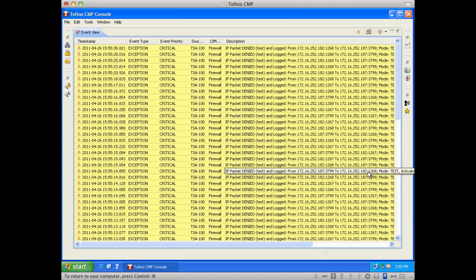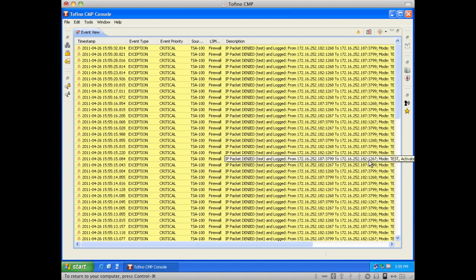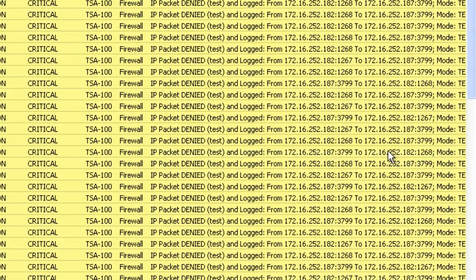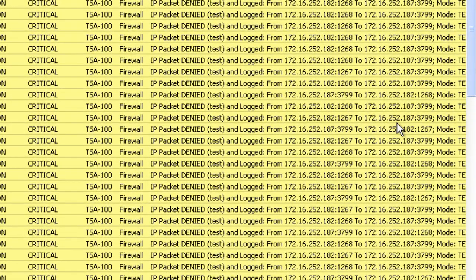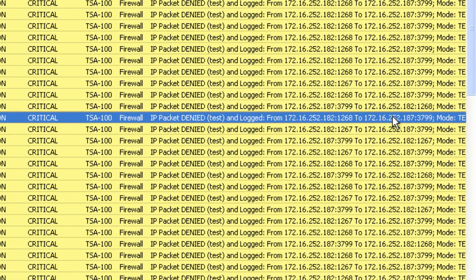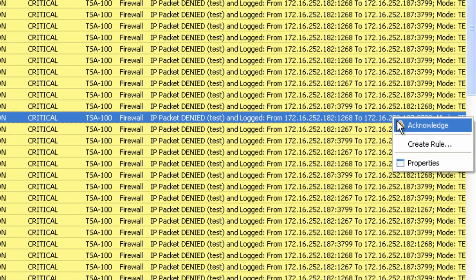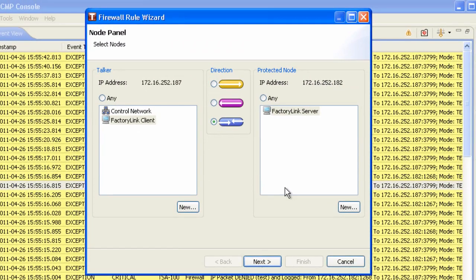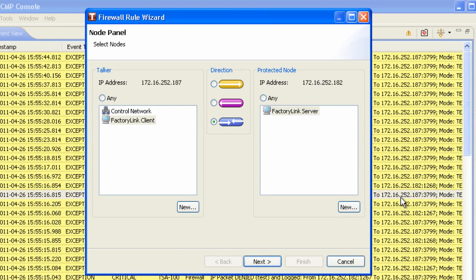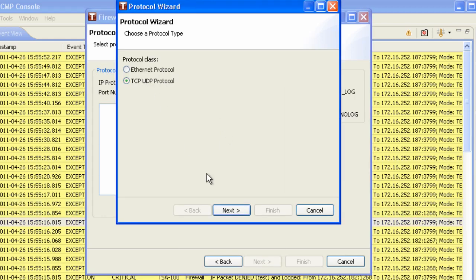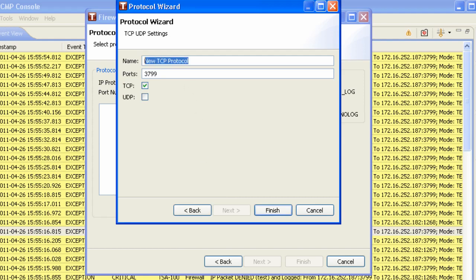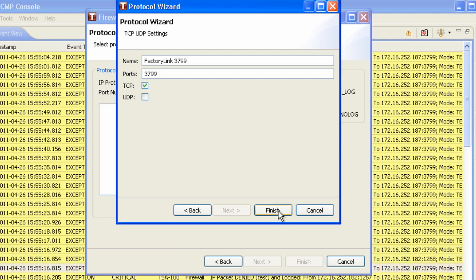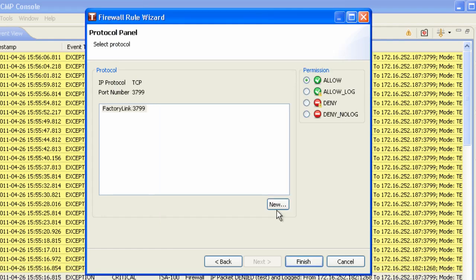And sure enough, if you remember, 3799 was one of the rules that we found or one of the service ports that we found when we did a Netstat. So I'm going to take this guy right here and I'm simply going to right click on it and I'm going to say create rule. And by looking at that packet, it knows the source and destination and the service that's being used. I'm not sure about this service right now. So I'm going to flag this as a FactoryLink service and I'm going to call it 3799 and I'm going to do some further investigation after we commission this.